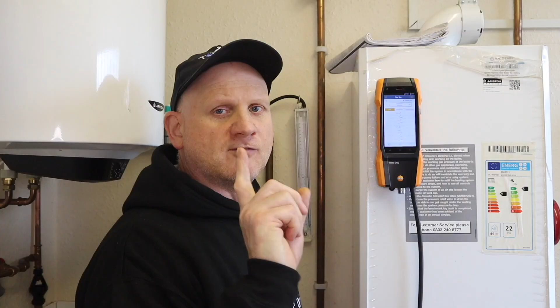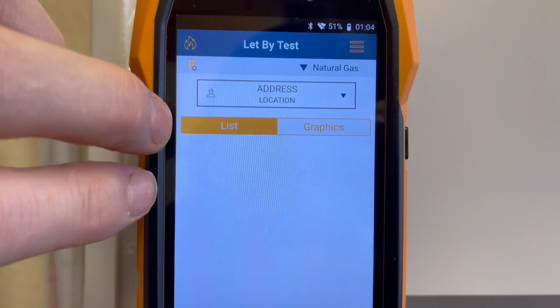First test we're going to do is a tightness test. First thing I need to do is set the analyzer up to tightness test. So I need to go into this little flame up the top, click onto that, scroll down to the bottom, because the first test we're always going to do is let by, isn't it? So we click on let by. And now it's switching. And it's come up with the let by test.